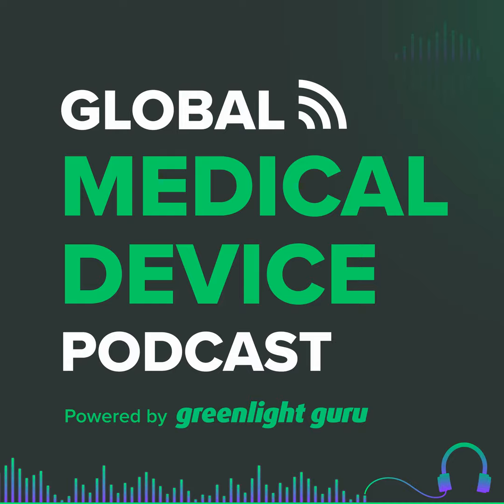So there's a little bit of nuance with that too, because some of the lower risk devices are what they call GMP exempt. So it's not automatically that all class 1 devices are GMP exempt. You really have to look into your specific product code and where it would fall and what that intended use is and what the FDA has decided. But even with GMP exempt, like a lot of government terminology, it's a little bit misleading. It doesn't mean you're exempt from having anything at all. It doesn't mean you're exempt from 100% of the requirements of Part 820. It means there are some things that you can omit.